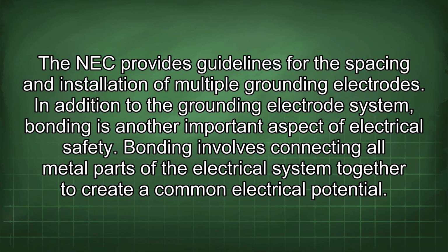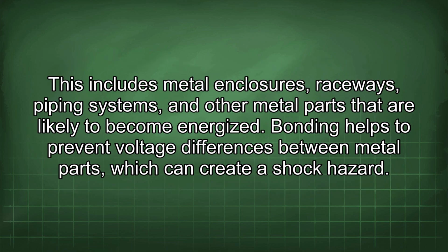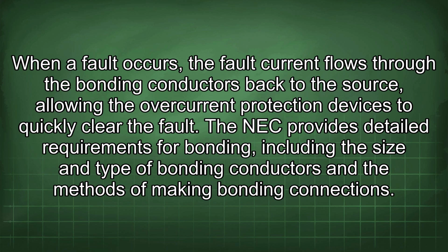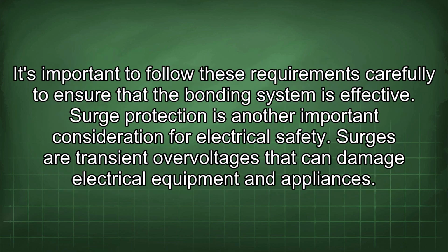In addition to the grounding electrode system, bonding is another important aspect of electrical safety. Bonding involves connecting all metal parts of the electrical system together to create a common electrical potential. This includes metal enclosures, raceways, piping systems, and other metal parts that are likely to become energized. Bonding helps to prevent voltage differences between metal parts, which can create a shock hazard. When a fault occurs, the fault current flows through the bonding conductors back to the source, allowing the overcurrent protection devices to quickly clear the fault. The NEC provides detailed requirements for bonding, including the size and type of bonding conductors and the methods of making bonding connections. It's important to follow these requirements carefully to ensure that the bonding system is effective.